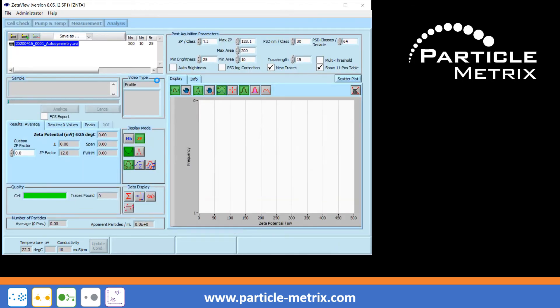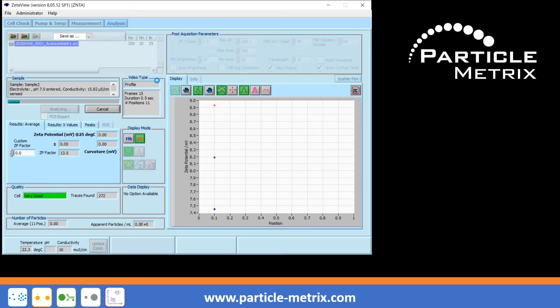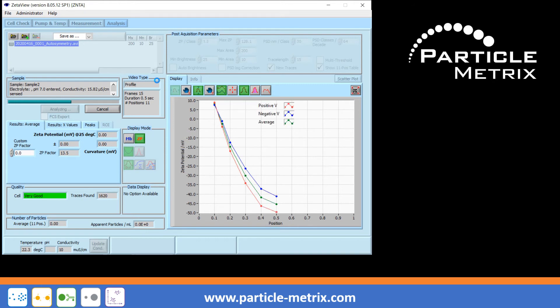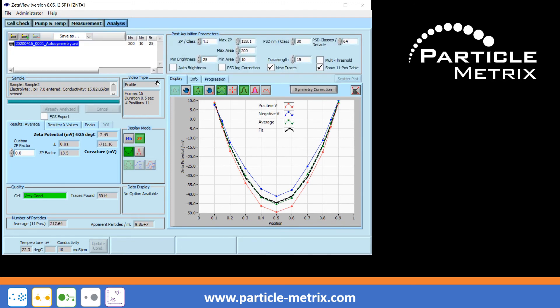As a result, a parabola is displayed. The quality of the parabola gives two statements. First, the symmetry of the profile with respect to the x-axis shows whether the optics has been aligned symmetrically. Any asymmetry will be corrected immediately after this test measurement.